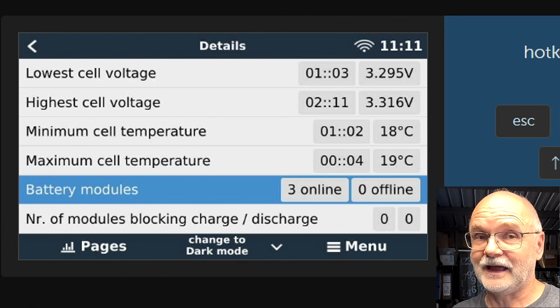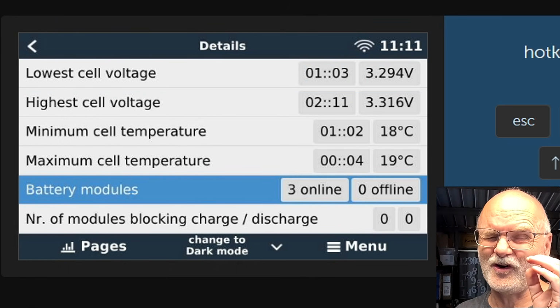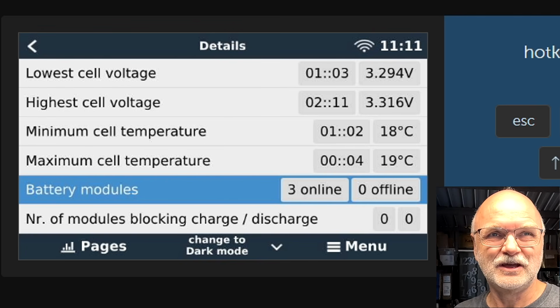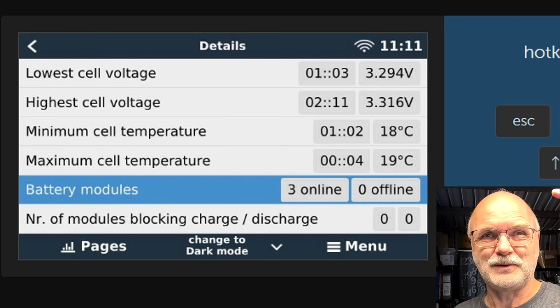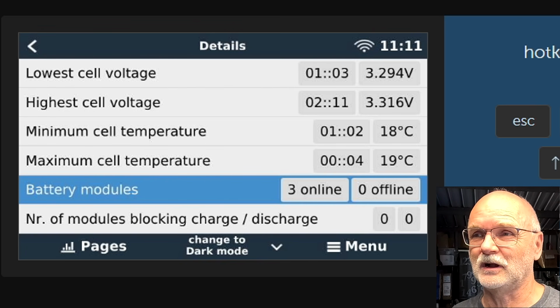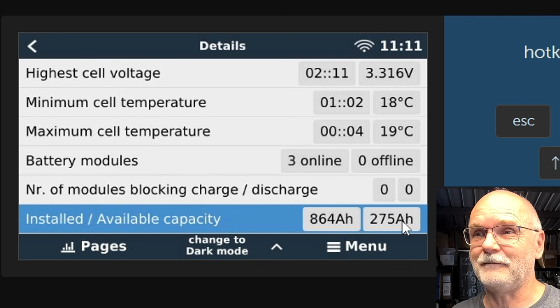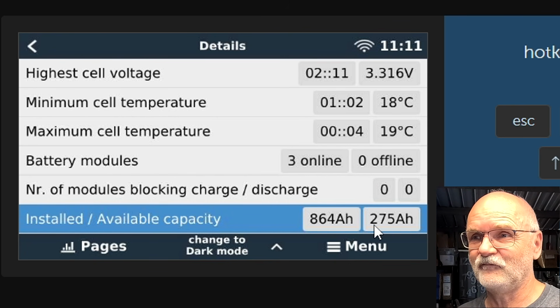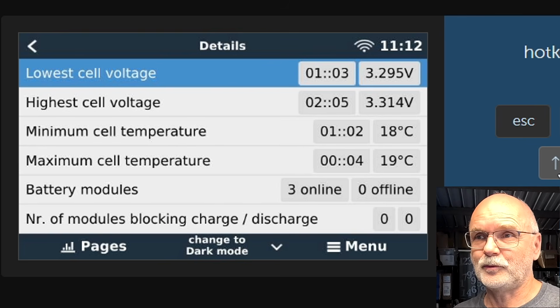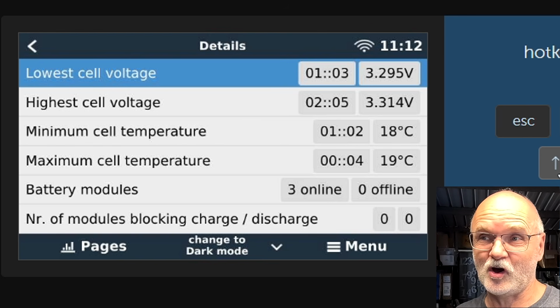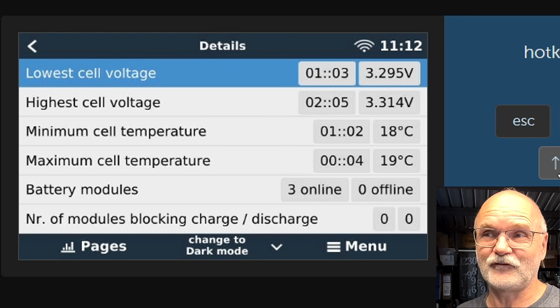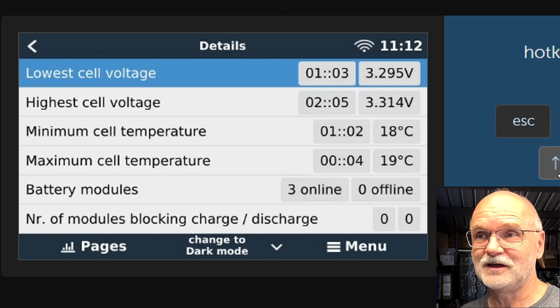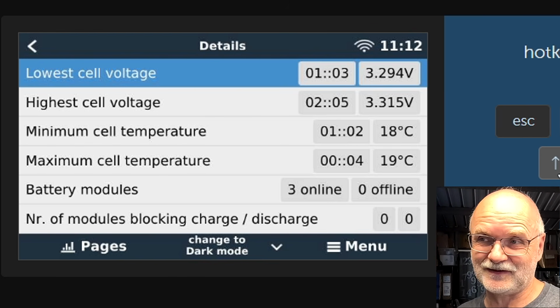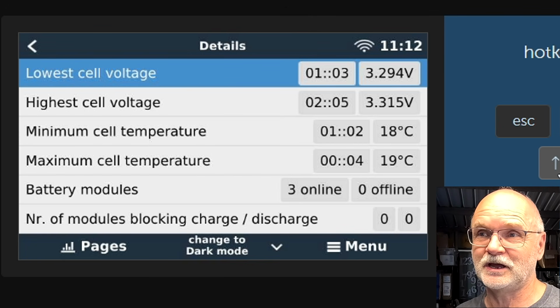All right. And we should see 864 ampere hours, if I'm not mistaken. 280 plus 280 plus 304 at the top shelf. 864, yep, there it is. And we have available 275 at the moment. So perfect. Communication works between the JK Inverter BMS in the top and the slave batteries' BMSs, which are JK B-series BMS with a P-link communication board.